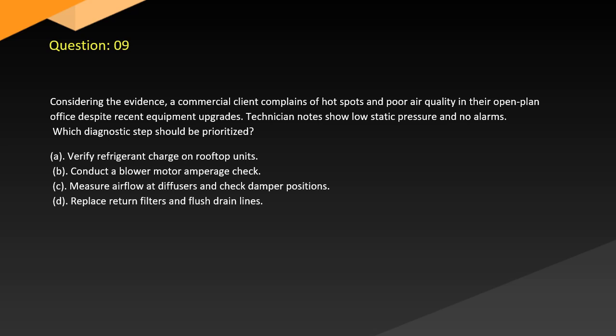Question 9. Considering the evidence, a commercial client complains of hot spots and poor air quality in their open plan office despite recent equipment upgrades. Technician notes show low static pressure and no alarms. Which diagnostic step should be prioritized? A. Verify refrigerant charge on rooftop units. B. Conduct a blower motor amperage check. C. Measure airflow at diffusers and check damper positions. D. Replace return filters and flush drain lines.